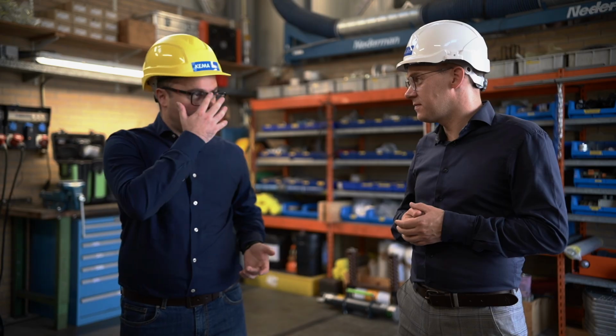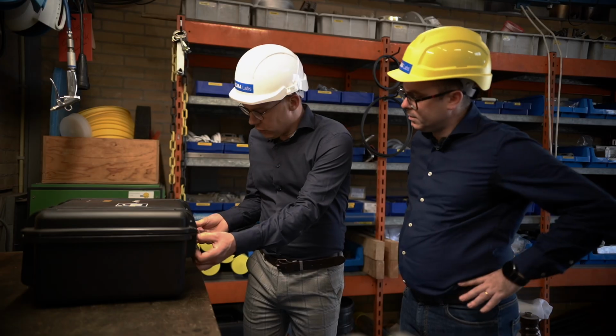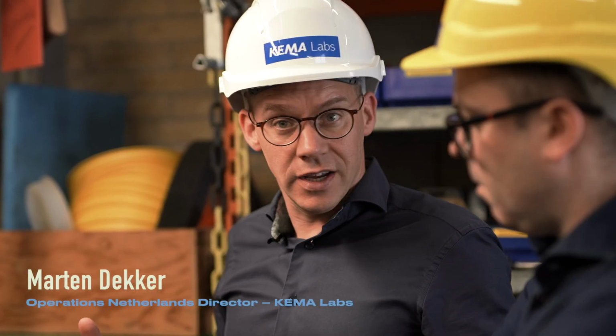Regarding the gas handling, did you procure or equip yourself with special equipment, with special devices to handle these operations? Yes, definitely. I can show you. The equipment we bought in order to safely test circuit breakers and equipment with alternative gases is several, and in principle it should cover the entire cycle. As discussed, the customer should have a one-stop shop. We can deliver them the gas, together with them we can fill the gas, then we can do the short circuit test in our laboratory, and we can evacuate the gas. And finally, we have to either recycle the gas or incinerate it, depending on the pollution level of the gas after the performed test.